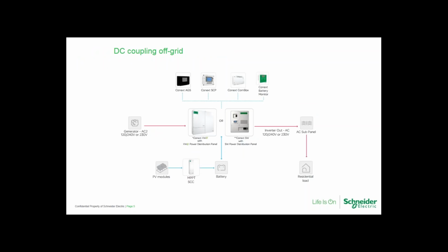DC coupling off the grid. PV supplies the charge controller, which in turn regulates and protects the batteries from overcharging. Loads will always have priority, so if the PV production is less than load demand, then that additional power requirement will be drawn from the battery. If the PV production exceeds the load demand, the excess will be used to charge the battery. Once the batteries are full, the PV production will be commensurate with the load demand. This means the charge controller will reduce power flow when there's excess PV energy over what the loads can consume, because that power has nowhere to flow.